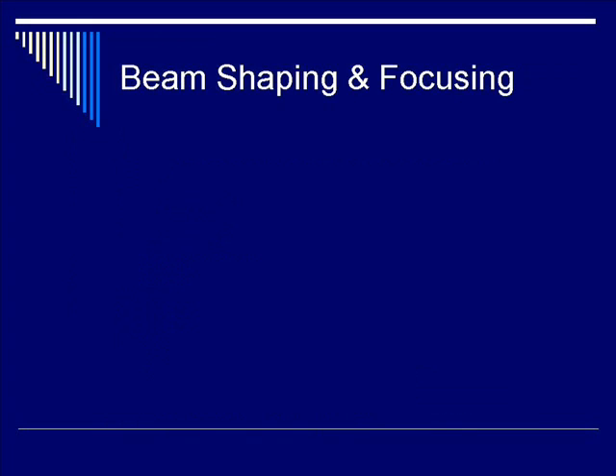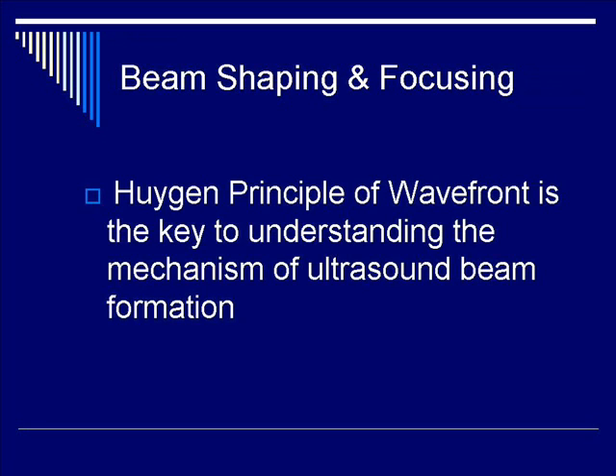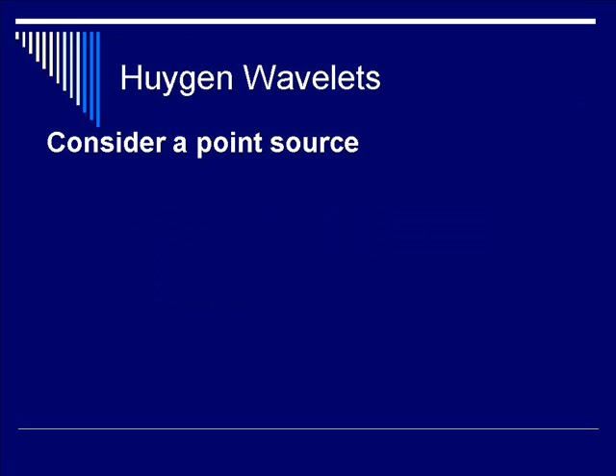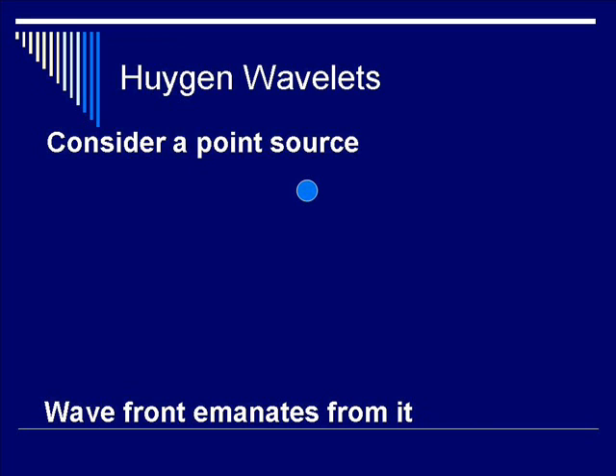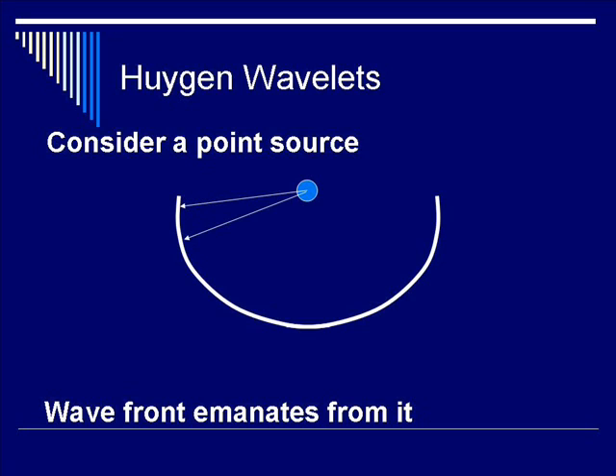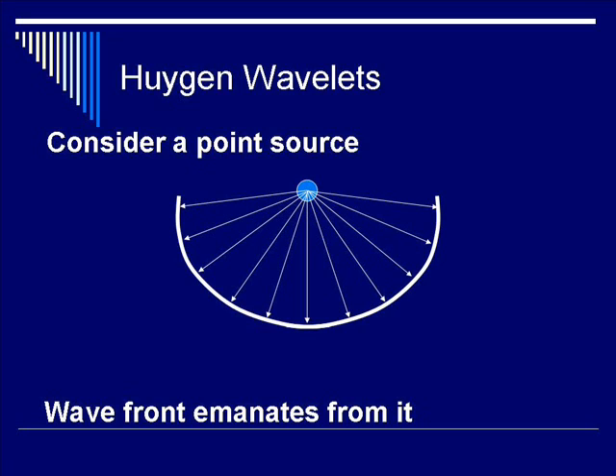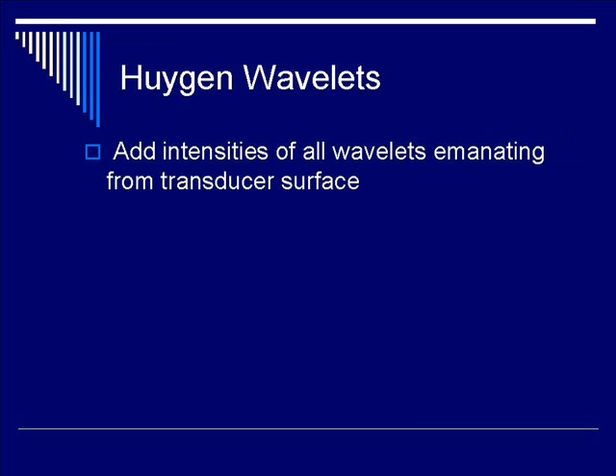We will now discuss ultrasound beam shaping and focusing. It is entirely dependent upon the application of the Huygens principle of wavelet formation and incorporation. Consider an ultrasound point source, denoted by the blue dot. A wavefront will be generated from this point source as it traverses towards the body tissue. The white line denotes the wavefront, which serves as the termination point of the various vectors emanating from the ultrasound point source. It expands with time as it traverses spatially. Ultimately, these Huygens wavelets can be added together to form the resulting wavefront of the transducer output.